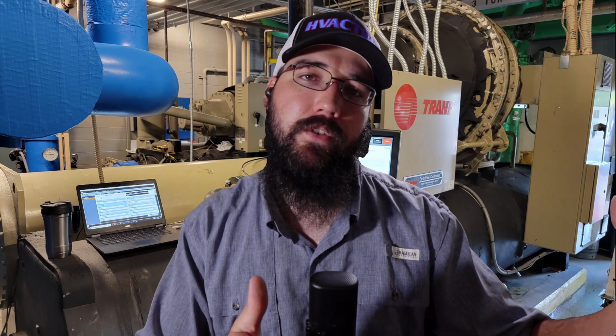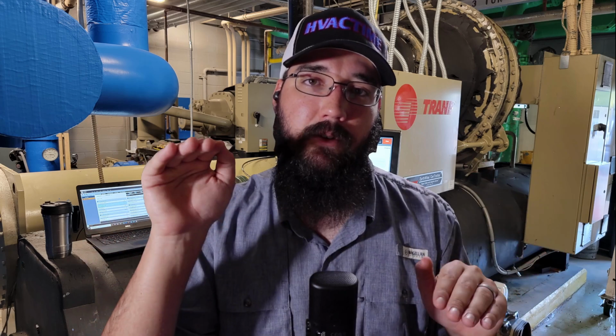So yeah, those larger blocks, you're probably looking at a single circuit water cooled style system. As we move into the air cooled side, and it gets split up between multiple circuits, I haven't seen one of those EXV blocks, those housings, on an air cooled. But when I do see them split, they'll do the tee thing where they'll just tee off the liquid line, go through two valves, and then tee back together on the other side. It is important that the lengths of all these things are very close to one another. In order to get proper flow and keep everything balanced and even, and one valve doesn't get favored more than the other, our lengths and our turns need to be on point. Otherwise, you can create different eddy currents that make the fluid move in ways we don't want it to.